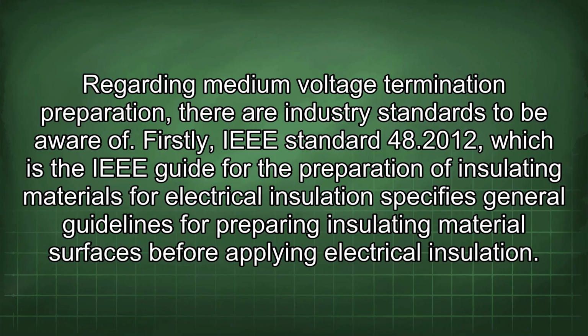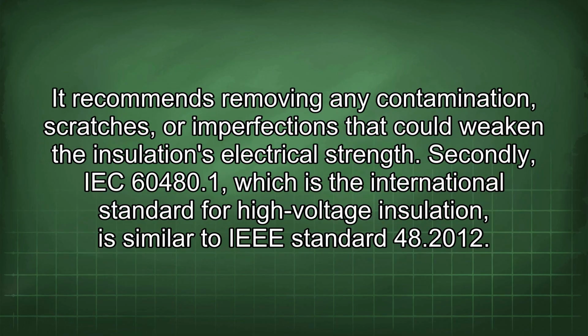Regarding medium voltage termination preparation, there are industry standards to be aware of. Firstly, IEEE Standard 48.2012, which is the IEEE guide for the preparation of insulating materials for electrical insulation, specifies general guidelines for preparing insulating material surfaces before applying electrical insulation. It recommends removing any contamination, scratches, or imperfections that could weaken the insulation's electrical strength.